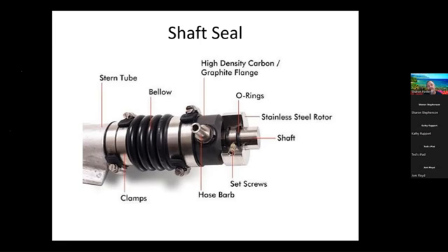And you got your different types, you got your bellows. This actually works like a mechanical seal, basically. The bellows and the graphite are stationary, and then you have the stainless steel rotor, which clamps onto the shaft itself, and that stainless steel pushes back against the graphite, creates a seal there. If these things are set up right, there's zero water comes in. The only downside to these is every 5 to 7 years you need to haul them and change out the bellows and have them serviced. But they are really good systems.